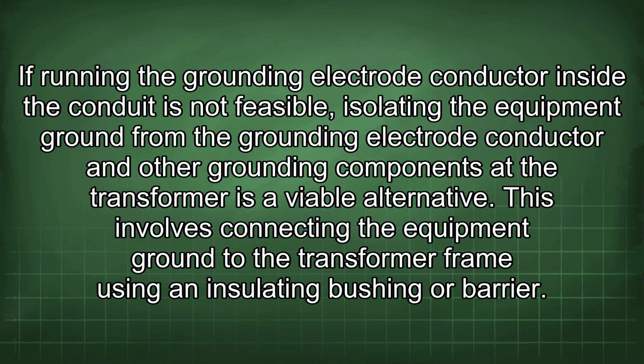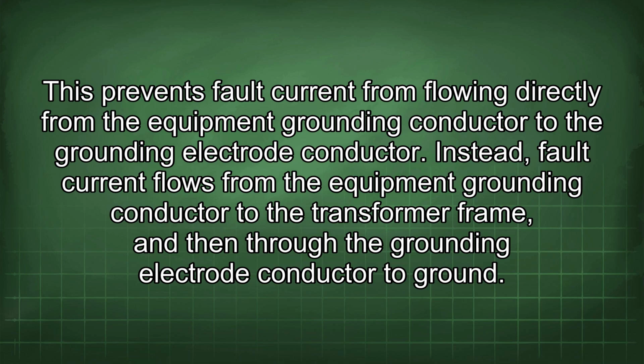If running the grounding electrode conductor inside the conduit is not feasible, isolating the equipment ground from the grounding electrode conductor and the other grounding components at the transformer is a viable alternative. This involves connecting the equipment ground to the transformer frame using an insulating bushing or barrier. This prevents fault current from flowing directly from the equipment grounding conductor to the grounding electrode conductor. Instead, fault current flows from the equipment grounding conductor to the transformer frame, and then through the grounding electrode conductor to ground.